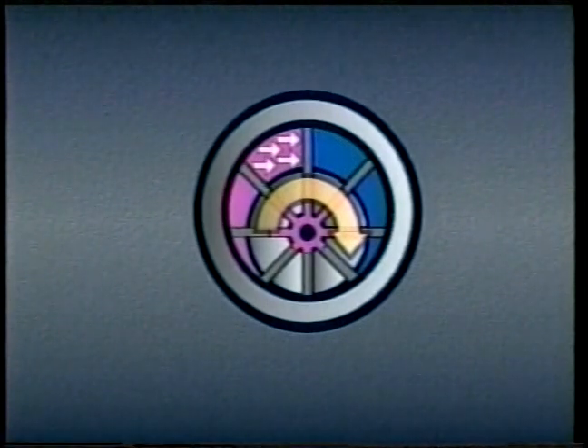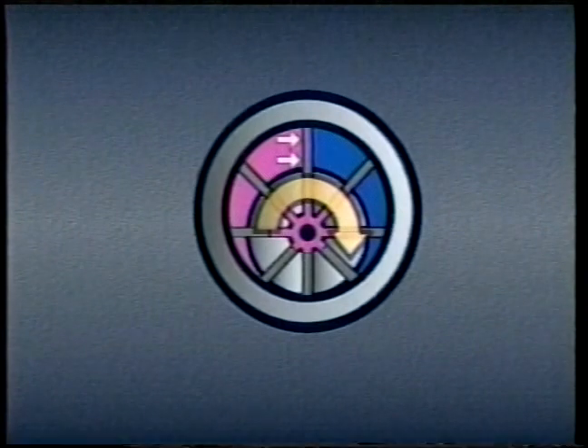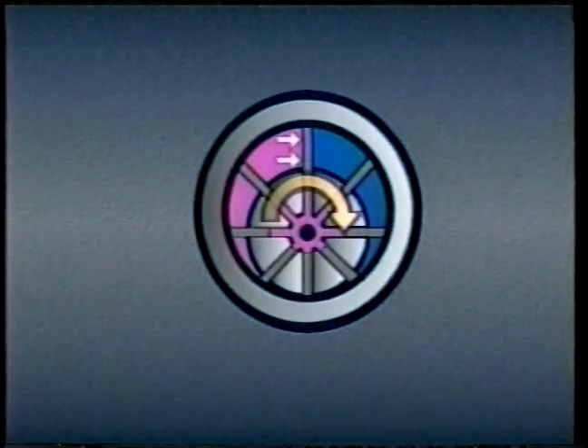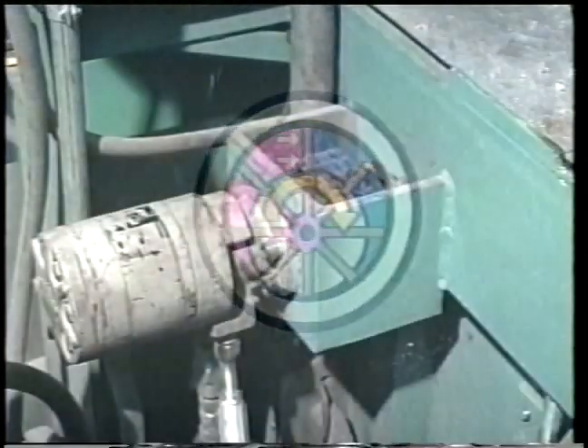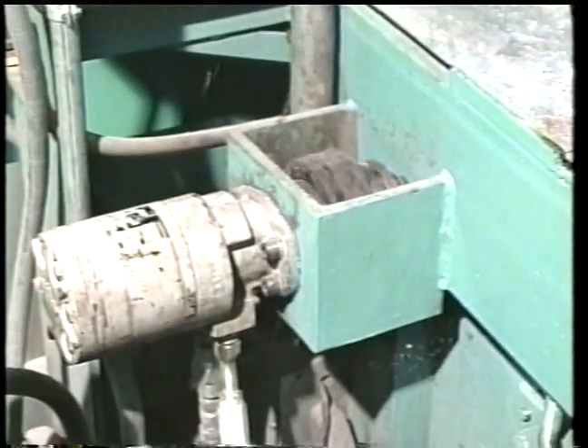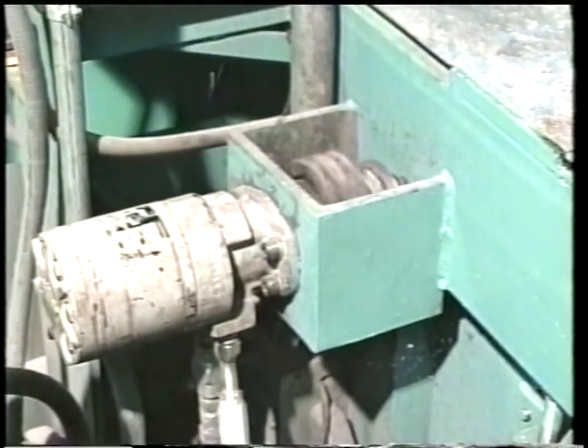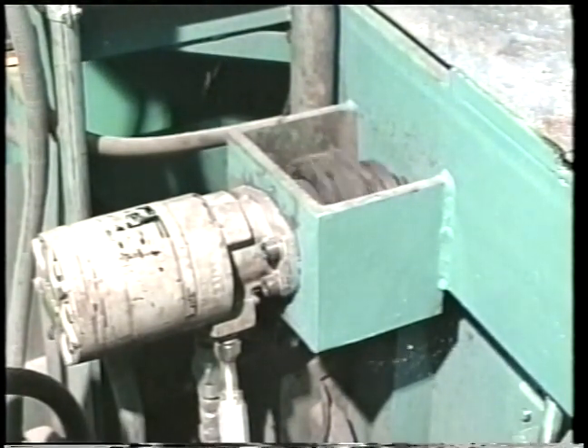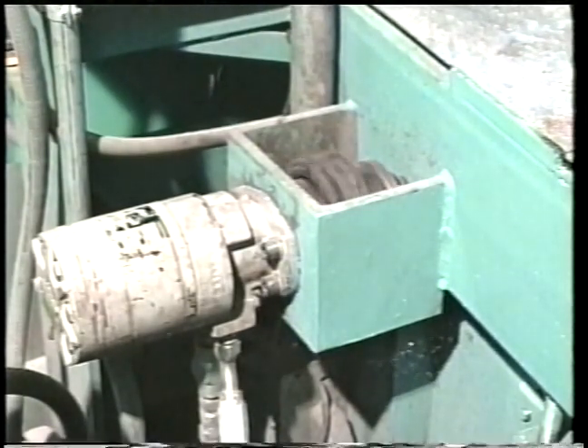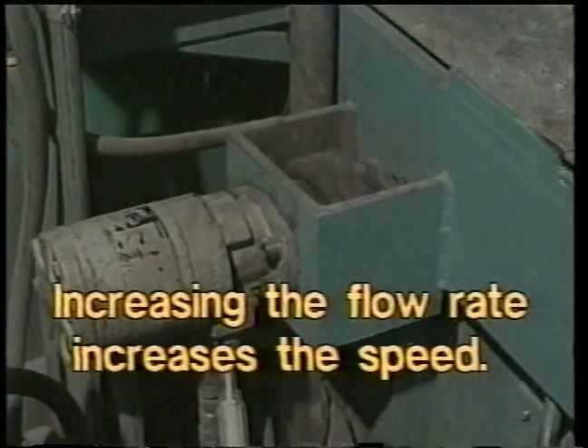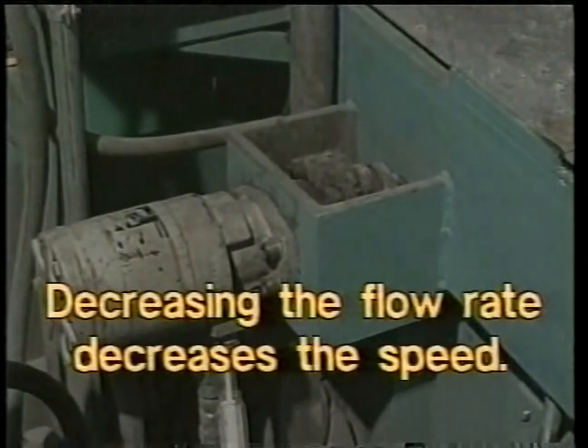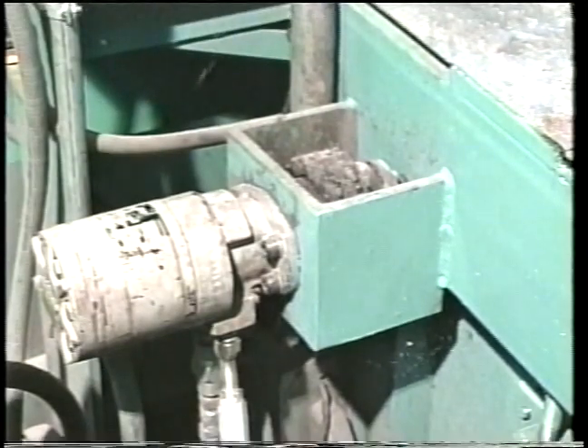As system pressure rises, the force applied to the vane increases, and the rotary force developed at the shaft, the torque, also increases. As long as the size of the motor remains the same, increasing the pressure will increase the torque. If pressure drops, torque drops. A similar relationship exists between flow rate and speed. If flow through the motor increases, then the vanes will turn faster and the speed of the shaft will increase. Again, this direct relationship between flow rate and speed is the same for all hydraulic motors. Increasing the flow rate will increase the speed, and decreasing the flow will decrease the speed, as long as the size of the motor remains the same.